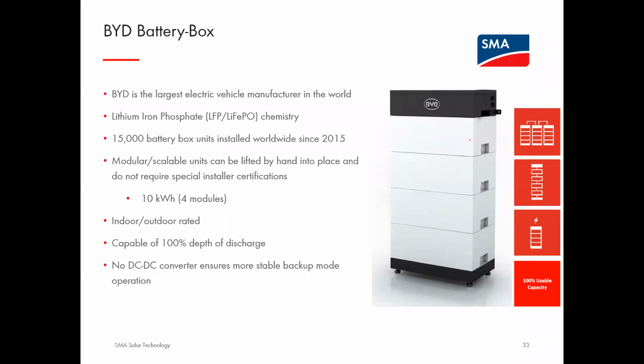If you can see my pointer here, each one of these is a 2.56 kilowatt hour building block, and you can stack up to 4 of them on top of each other to get just over 10 kilowatt hours. The thing I really like about BYD is that each of these building blocks weighs only about 80 pounds. So getting them on and off the truck, getting them into the house or into the basement is a lot easier than dealing with a large single unit battery. It is capable of 100% depth of discharge and is also indoor-outdoor rated. And because there's no DC to DC converter in the BYD battery, we see that it delivers quite stable backup mode operation. The microgrid operates in a very stable condition.